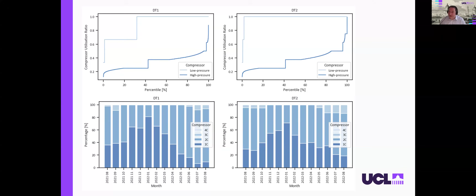This is a stat showing that out of 4 compressors, only 1 is running more than 45% of the time throughout the year. 2 out of 4 run 95% of the time. That means there's a lot of spare capacity in already existing equipment which we might utilize to harvest the rejected heat.